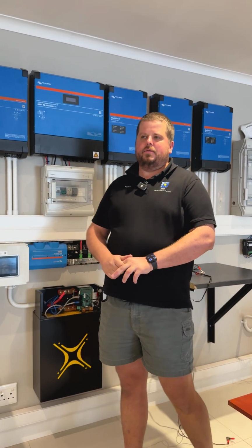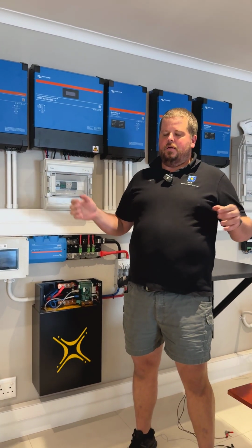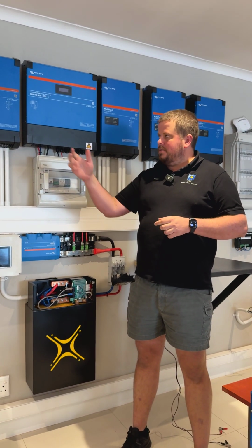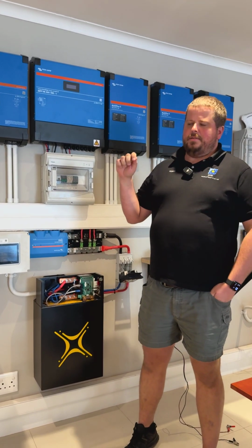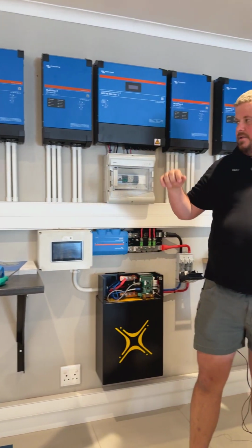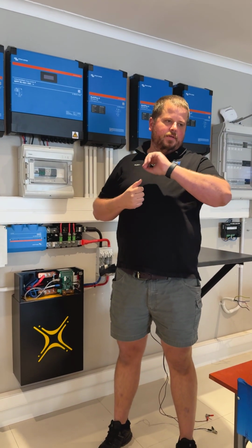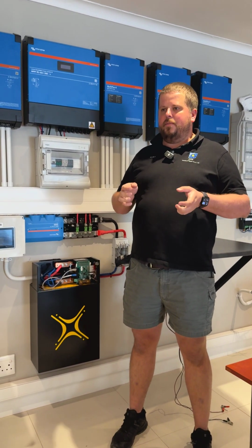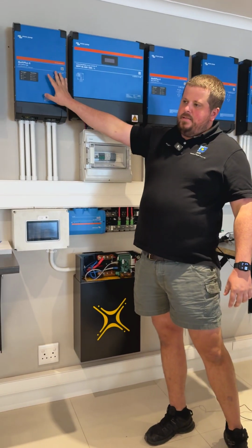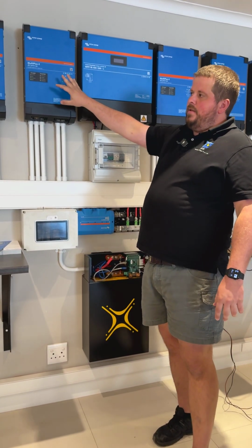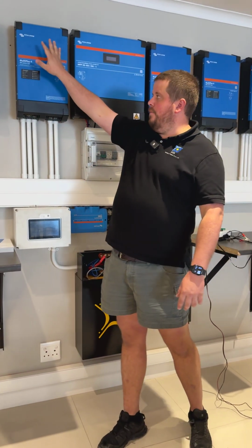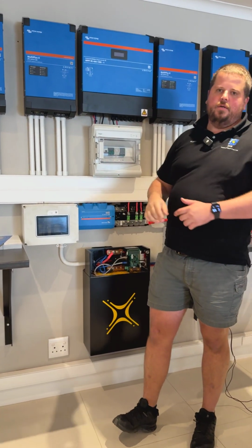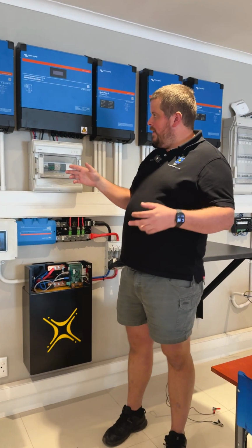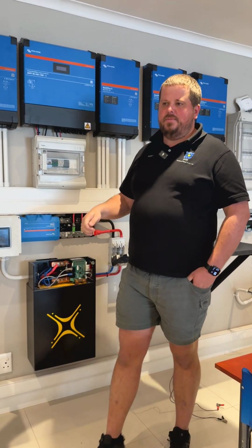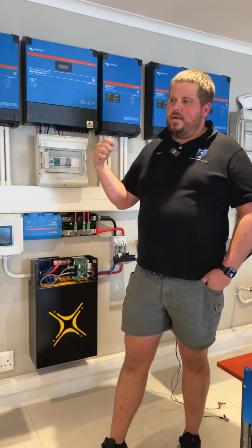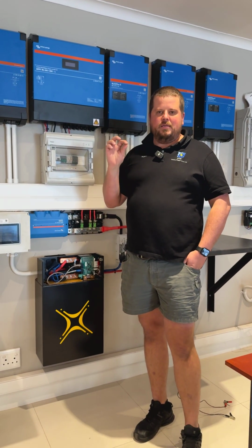Today we're touching on a sensitive industry standard in solar. People believe there are multiple stories going around - one says pre-charge from the AC side, one says pre-charge from the DC side. Let me explain plain and simple: this is not a grid tie or high frequency inverter, this is a transformer based battery-based inverter. By basic meaning, a battery-based inverter must start from the battery side. Yes, you can start from the AC side, but personally I believe it's not good practice.